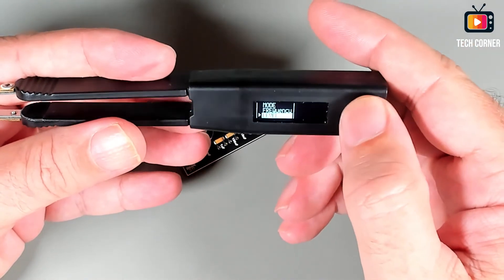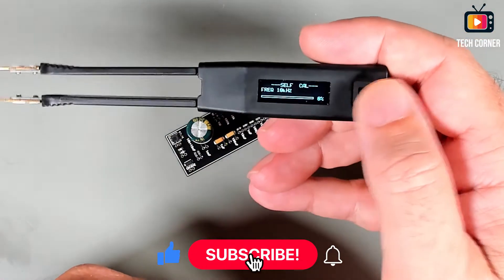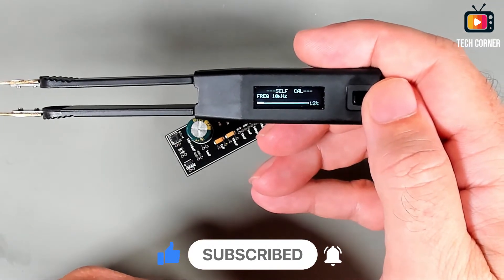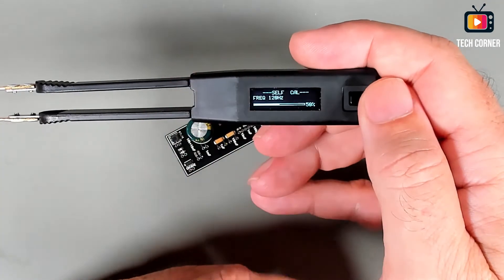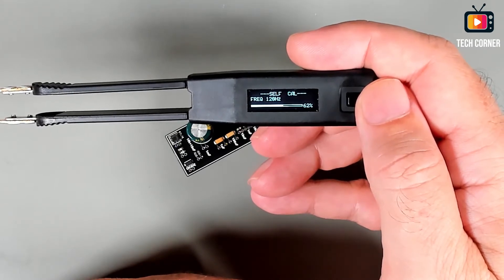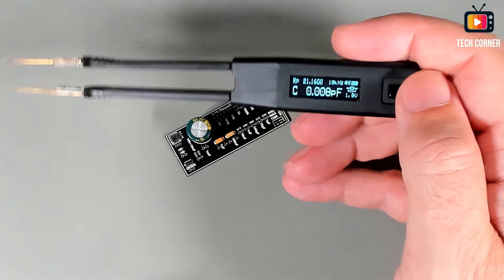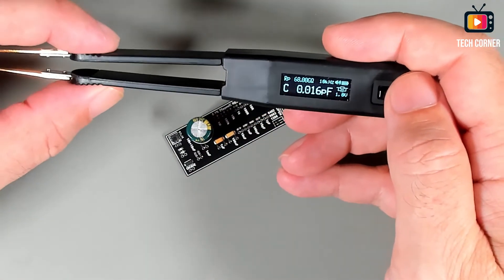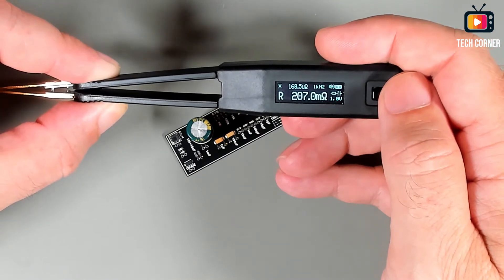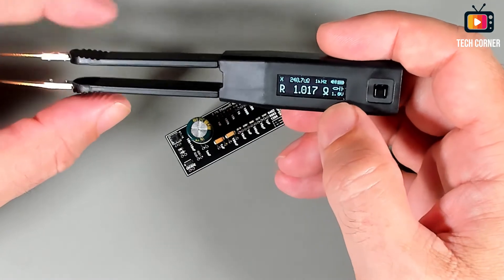For calibration, let's go to the measure menu and then calibration. The first step is self-calibration — just press and wait about 30 seconds. It will test all frequencies: we're testing 120 Hz now... and done. As you can see, capacitance reads 0.05 — almost zero. Testing resistance, it's well below 20 ohms, which is the threshold value considered for continuity. The self-calibration is complete.